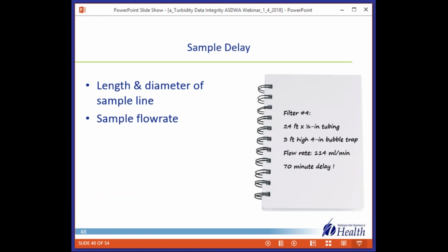Yeah, so sample delay. This is from an actual treatment plant, and it's an example of what you don't want to have. So you take a look at this. This was a plant that had been retrofit, so putting some new into an old box, so that made it a little hard. Filter number 4 had 24 feet of, I think that's ½ inch tubing. They'd been having trouble with bubbles, so they put in this big bubble trap, 3 foot high, 4 inches in diameter, and the flow rate was only 114 mils per minute, so it was actually below the range that was specified for that turbidimeter. That turns out to be a 70-minute delay.